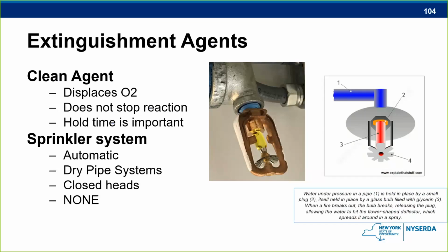That clean agent, as a rule of thumb, will take out some of the oxygen. So you better be on your SCBA if there is a clean agent, and you really shouldn't be going in there. But you don't want to open up a doorway to a room or an enclosure that has released its clean agent, because it's not a good place for us to be. And also there is a hold time that needs to take place. These things don't happen immediately. There is an amount of hold time that needs to take place for it to do its thing and put the fire out.